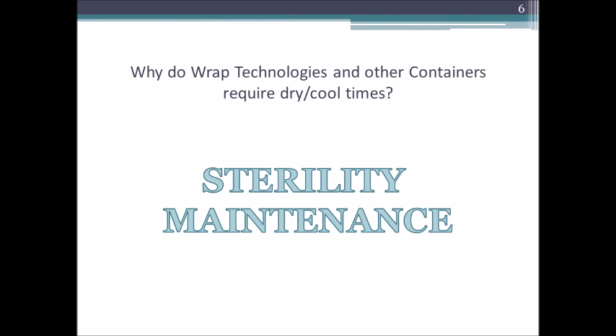Even in the world of containers, like these 40-year-old devices, it can become a problem because the design of their locking mechanisms and filter systems could allow water to come from the outside in, carrying contaminants with it. So they want their devices to be dry from the time they come out of the sterilizer, this way there's no chance for contamination.